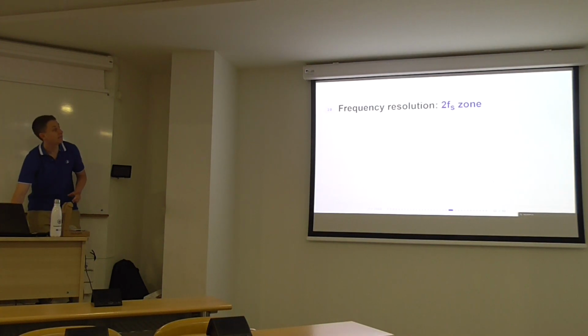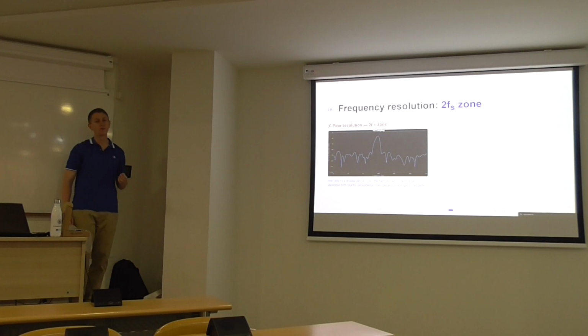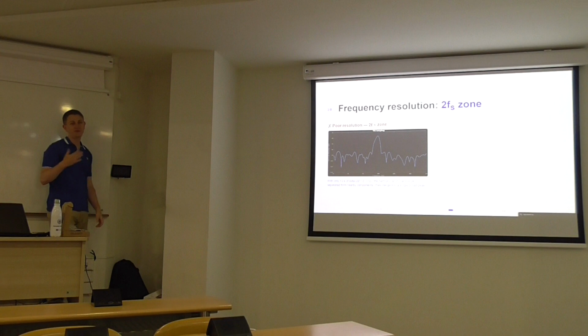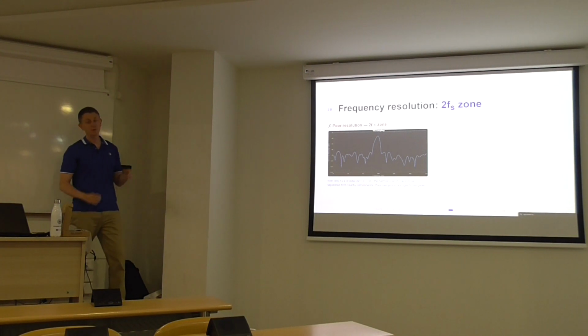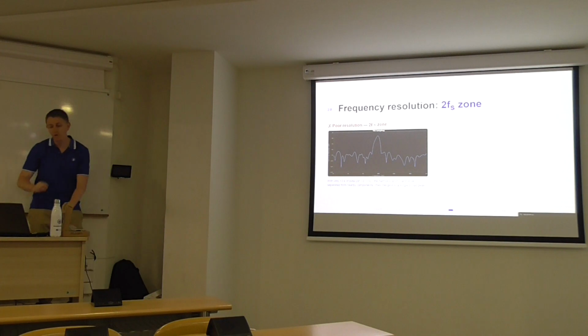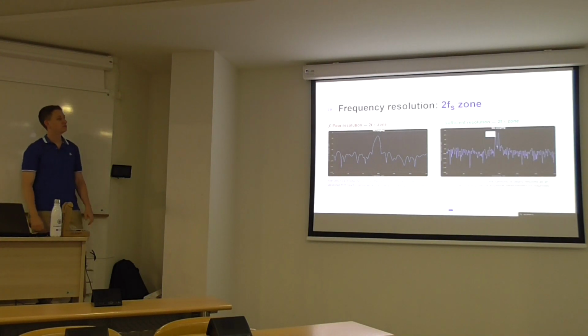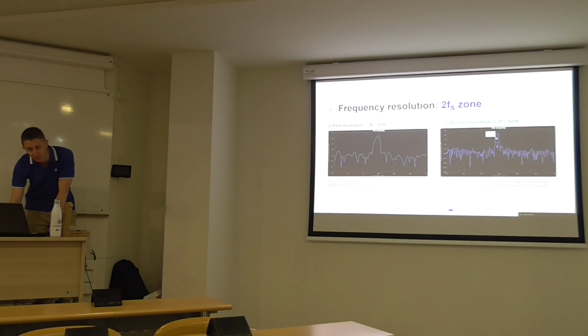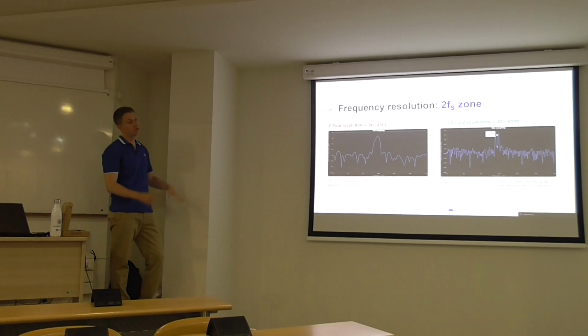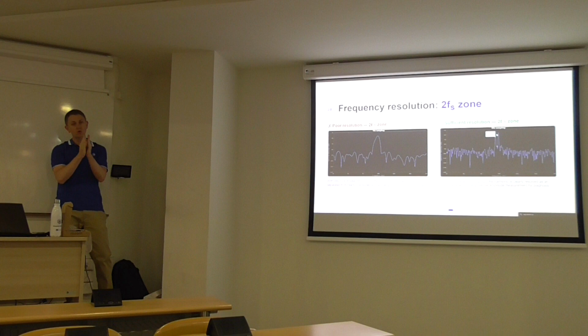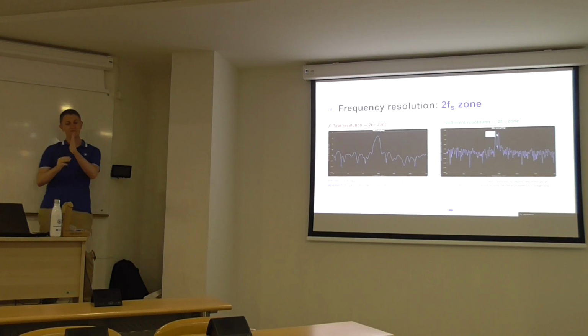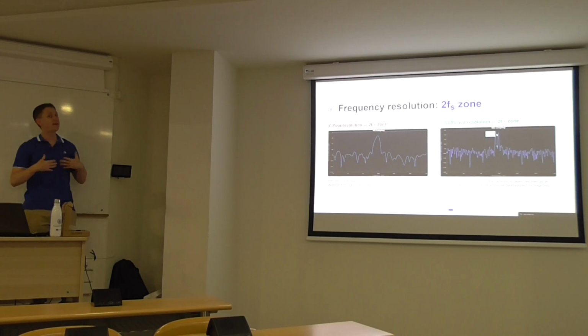Now let's take a look at the upper mixed eccentricity harmonic, which appears in a 2-pole machine to the left of 100 Hz if we are feeding the motor with 50 Hz. Okay? If I look at the spectrum with only 10 seconds, what I see here is just a single peak. I don't know if that is the mixed eccentricity harmonic or just a multiple of the fundamental component, a non-related fault. However, if I increase the frequency resolution, now I can clearly see the two peaks, the mixed eccentricity harmonic and the multiple of the fundamental component. So with low frequency resolution, you only see one peak because they are so close that they merge into one. But if you increase the frequency resolution, you can define perfectly the mixed eccentricity harmonic and next to it the other harmonic, okay? It's always important to have enough frequency resolution.